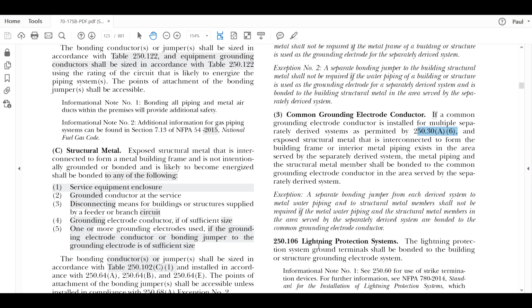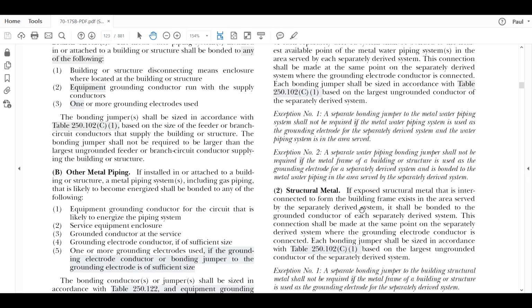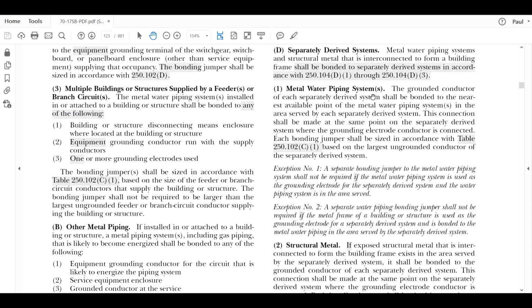Okay, now again, we have some exceptions. I really wasn't going to get into these, but I'll talk about one of them and move on. You want to read them yourself. They're not complicated, you just have to read them. The general rule here was to take it to the water pipe, right? And it says that you would use 250.102(C)(1) to do it. So this is the rule. So there are exceptions. The exception says a separate bonding jumper to the metal water piping shall not be required if the metal water piping system is used as a grounding electrode for the separately derived system and the water piping system is in the area served.